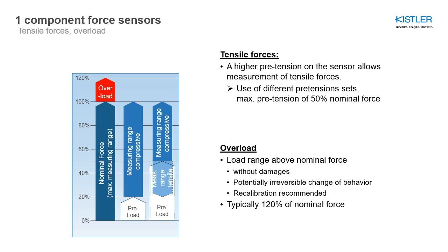One of the biggest advantages of a piezoelectric force sensor is its ability to survive overload. We define in the datasheet an overload of typically 20%. That means we allow 120% of nominal force and guarantee that there is no damage at all. However, we recommend to maybe calibrate it again, because it might be that the behavior has changed slightly if you overload it several times.